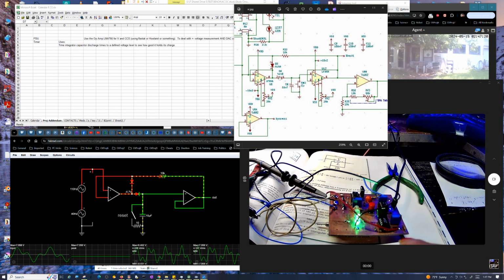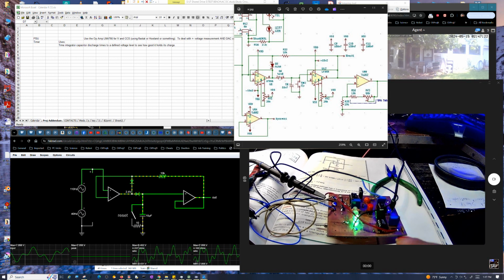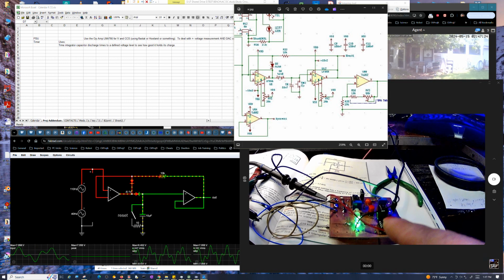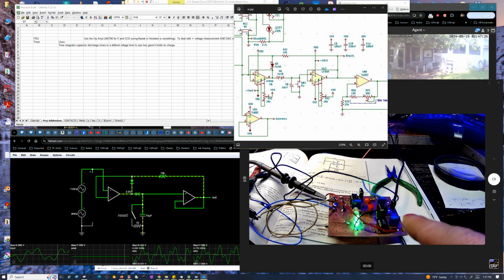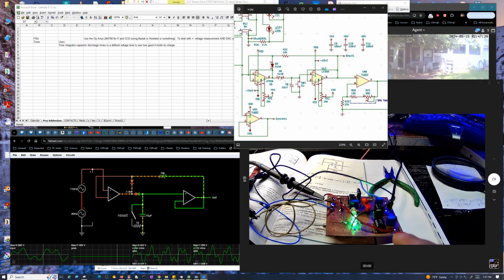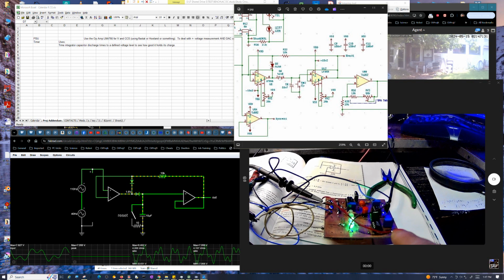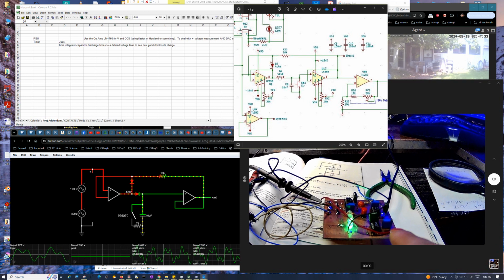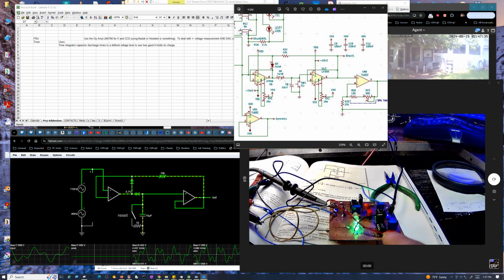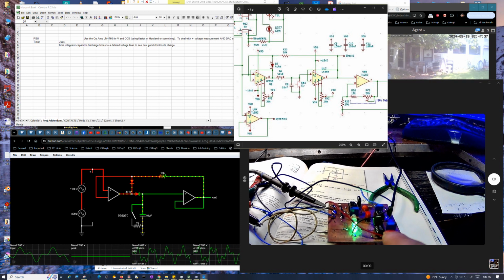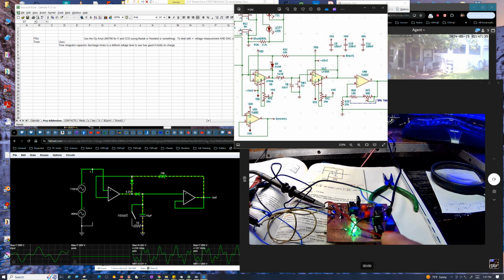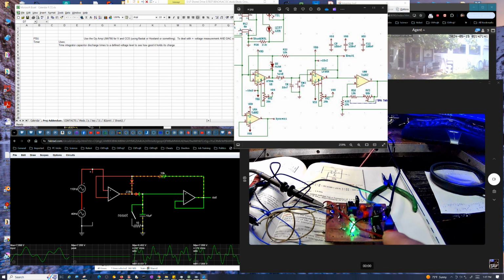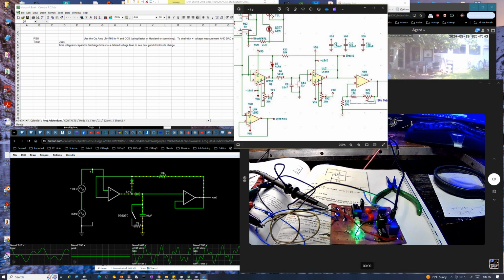Or if it's a 50 amp shunt, it's going to be 666 millivolts across that resistor as the output, ideally. But that would show up as, with 1 millivolt, looking like we got 600 milliamps on a 50 amp shunt, or on a 5 amp shunt that we got 66 milliamps instead of 666.